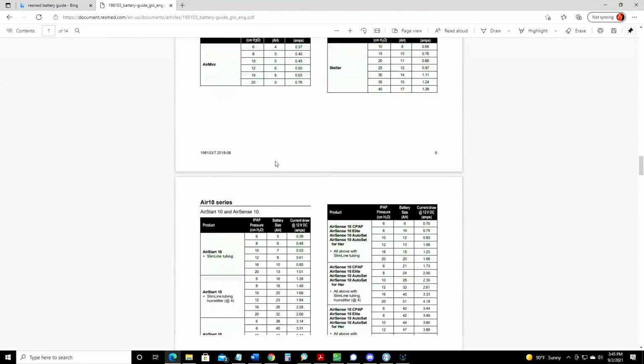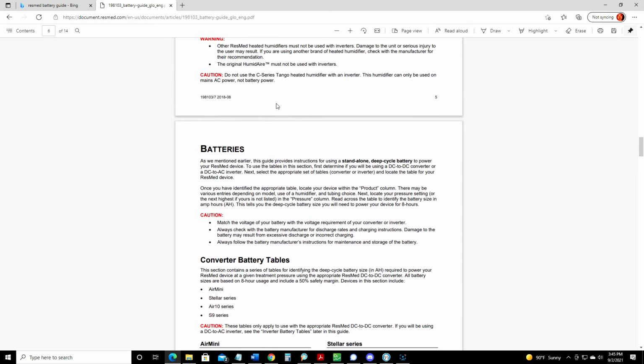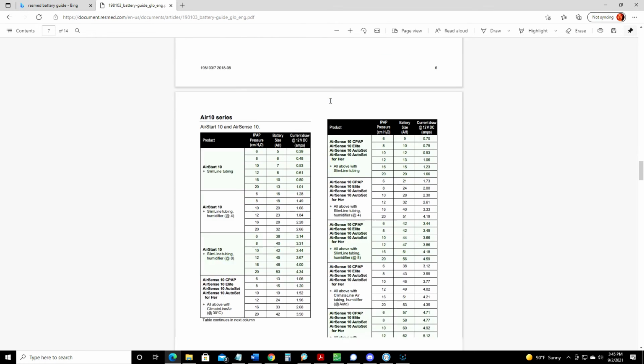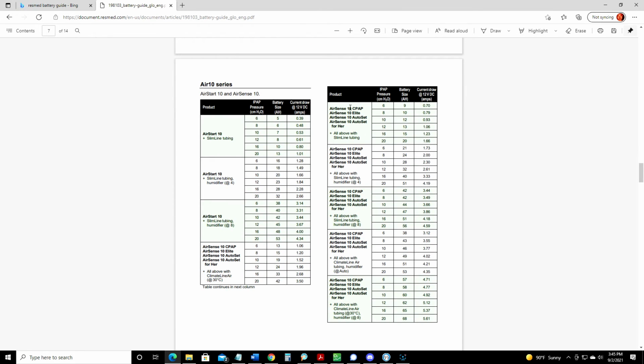So anyway, what am I looking at here? Converter battery tables. I'm looking for AirSense 10. That's going to be right here in this column. And then one thing you can really see here is that, this is your pressure. This is the battery size that you need. We'll really ignore the current draw because that's not a factor. But if I were not using any humidifier at all, well, I'm somewhere between the 12 and 16. So I would need somewhere between 13 and 15 amp hours to power it.